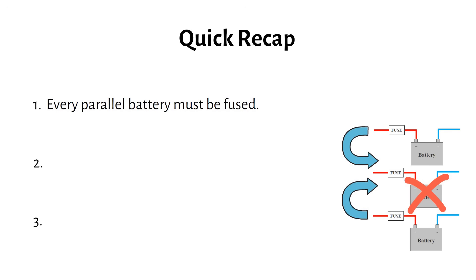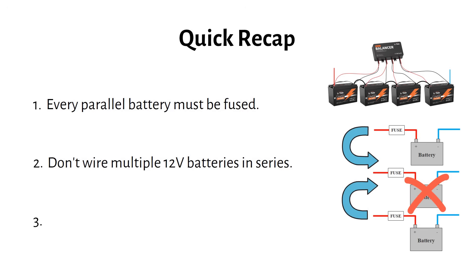Second, if you're building a 24 or 48 volt system, use 24 or 48 volt batteries. Don't wire multiple 12 volt batteries in series. This creates unnecessary complexity because batteries in series don't balance themselves. You'll need to add balancers. Batteries in parallel, on the other hand, balance themselves. That's why parallel connections are always preferred.